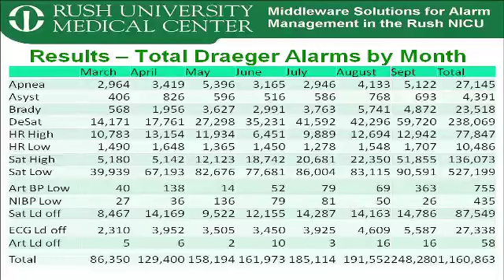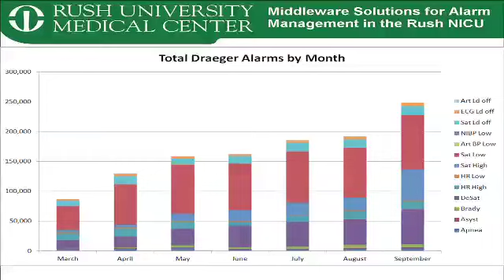When you look at the actual numbers, you can see overwhelmingly the majority, in this case half of them, were the low saturation alarms, and then the critical DSAT is another 230,000. So between those two, it accounts for almost 3/4 of the alarms. This is one of the big frustrations. The high saturation also is pretty high. So when you take all of the saturations away, the numbers go down dramatically. This is what those look like if you plot them by month. September was a particularly high acuity month, and March was only part of the month.